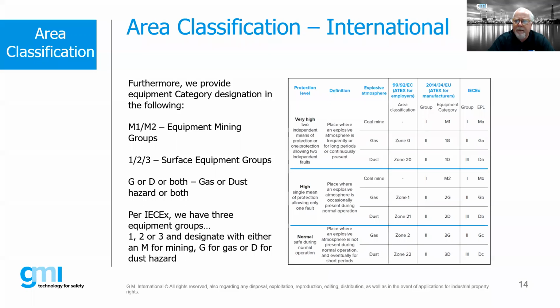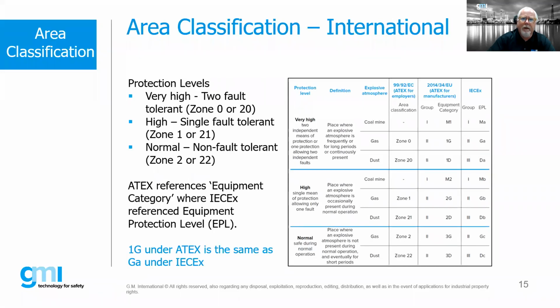And then finally, a product that doesn't have any fault level protection, but is safe during normal operation, would be suitable for an environment in which a gas, vapor, or dust hazard is not present during normal operation. But if it will be, it will only be for very short periods of time. So think of it this way: very high would be a zone 0, high would be zone 1, and normal would be zone 2. So I just mentioned this already in my slides here.